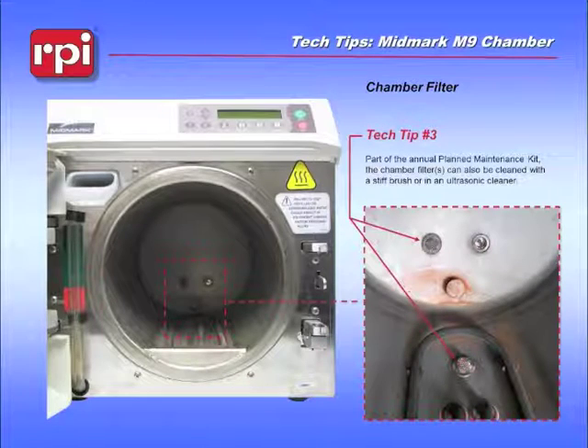Back here in the rear of the machine, we have our temperature sensor. That's the device over here on the right-hand side. It needs to be clean and not have any calcium or lime built up on it. We also have our water level sensor. That's this round disc. The water will fill up until it contacts this device. And we have a series of 2 filters that keep material from the packs or the instruments from getting into the valves. That will extend their lifespans. We replace those on a yearly basis, or they can be cleaned in an ultrasonic cleaner.